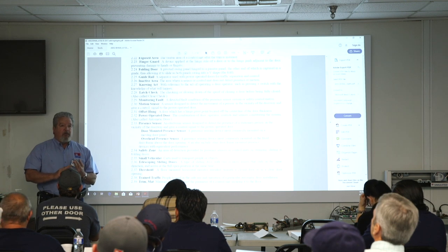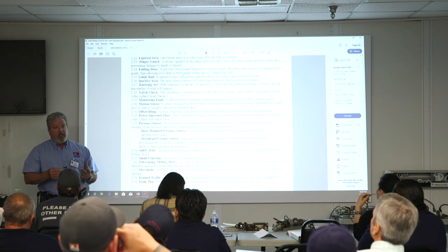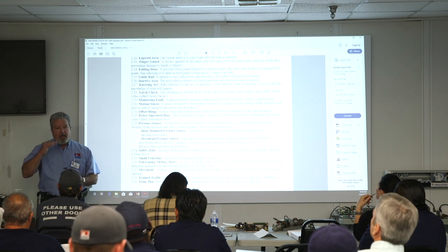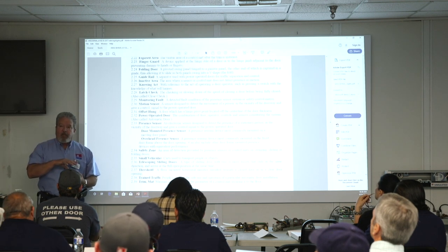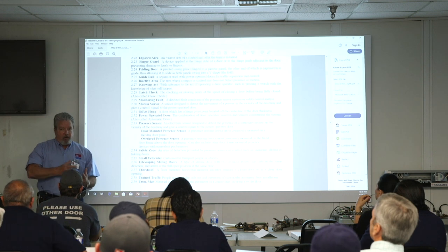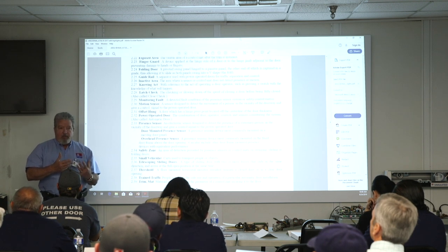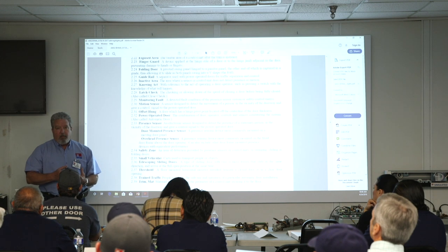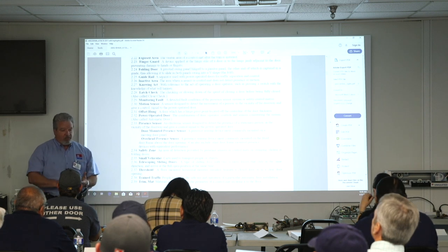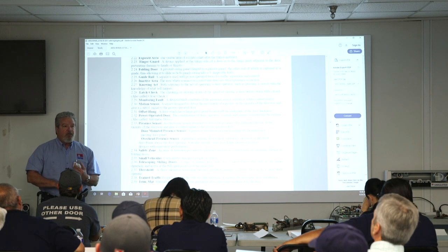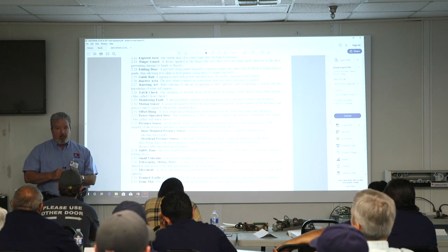The other form of motion sensor uses active infrared. Active infrared is basically light beams at a level that you can't detect with your eye. It emits light energy, and it is also looking for reflected energy back, but light energy and not microwave energy. And when it detects motion, it causes the sensor to signal the door. So motion sensors rely on motion. Most common is microwave, but there are some active infrared motion sensors being used today.